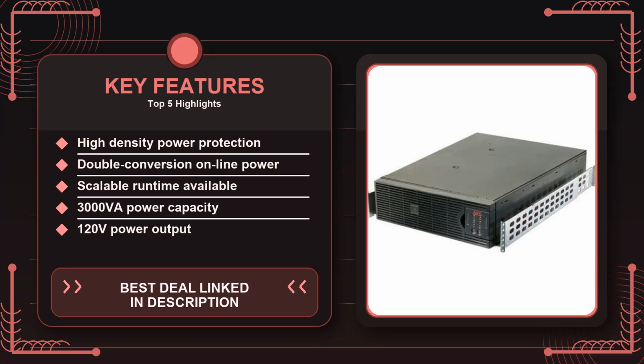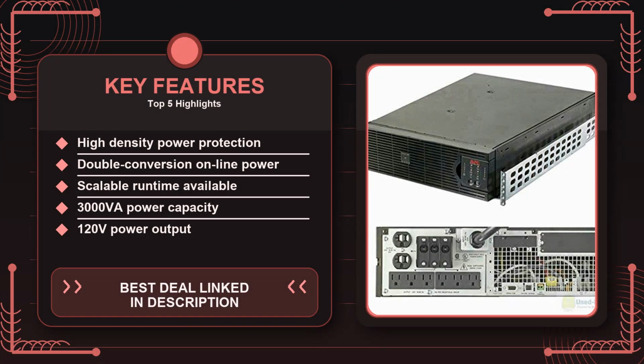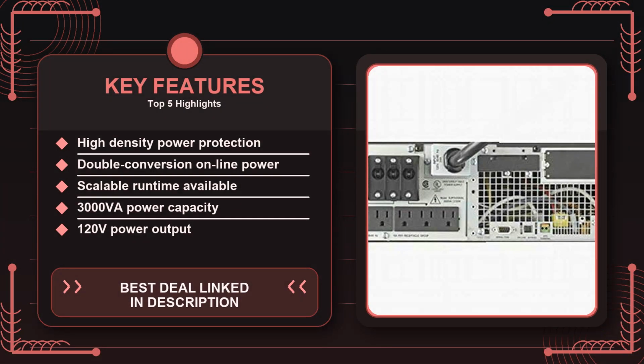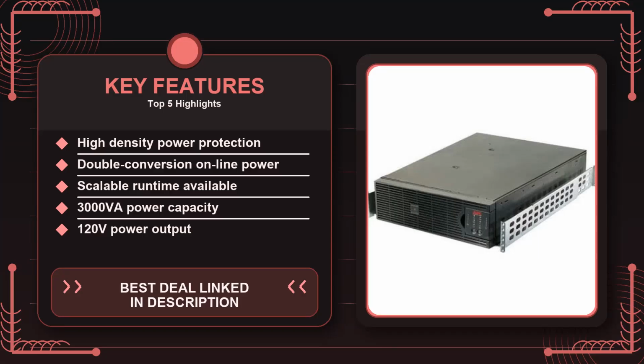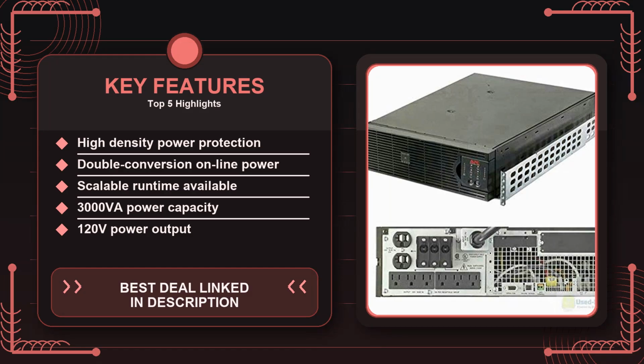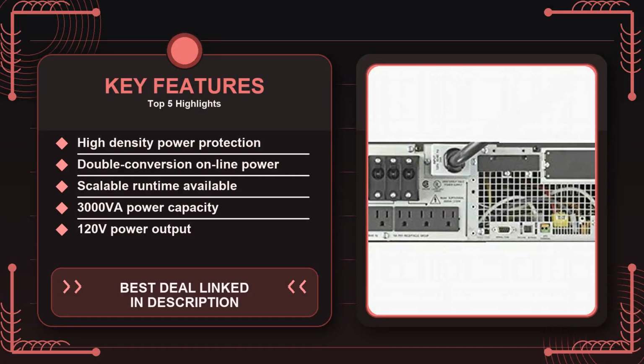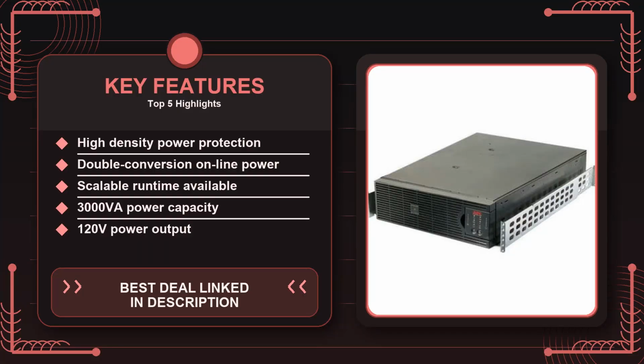The UPS also includes hot swap capability for the power modules. If you ever need to replace a power supply without taking the unit offline, you can do so while it's still running, provided the load is within the remaining module's capacity. In practice, this translates to less downtime for critical equipment, a factor that many IT managers overlook until a module fails. The double conversion design, combined with hot swap, gives a level of redundancy that's usually reserved for much larger, more expensive UPS systems. But there are a few trade-offs that potential buyers should be aware of.